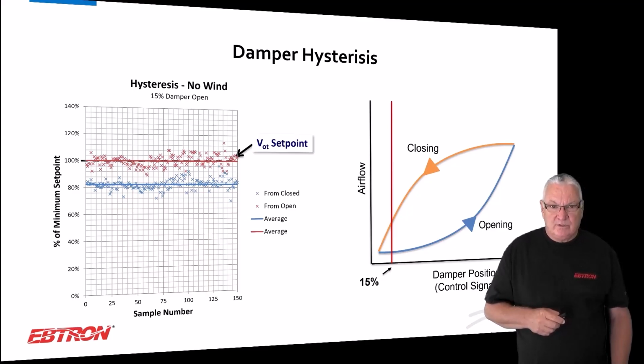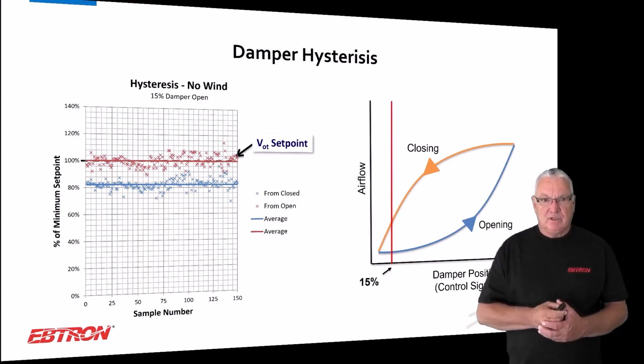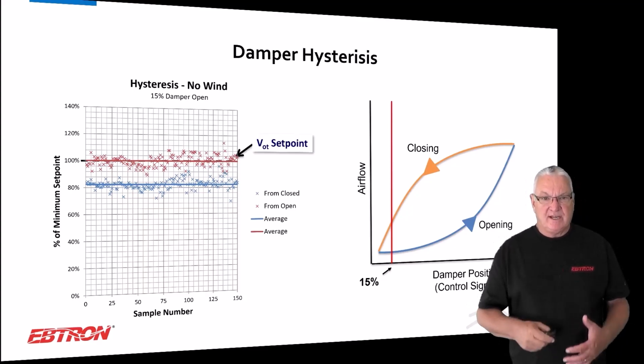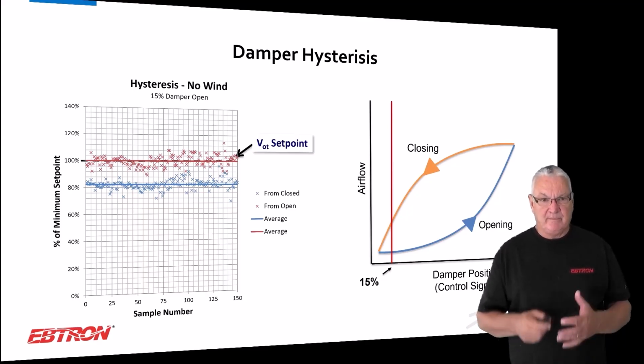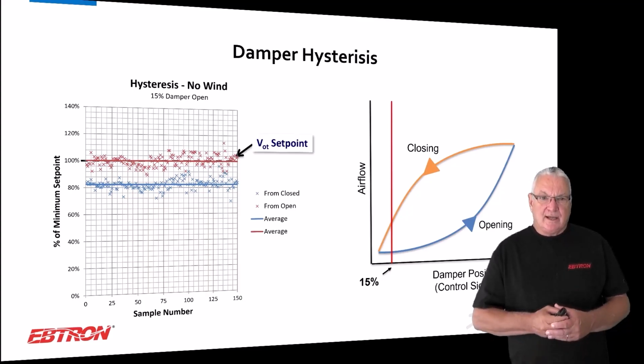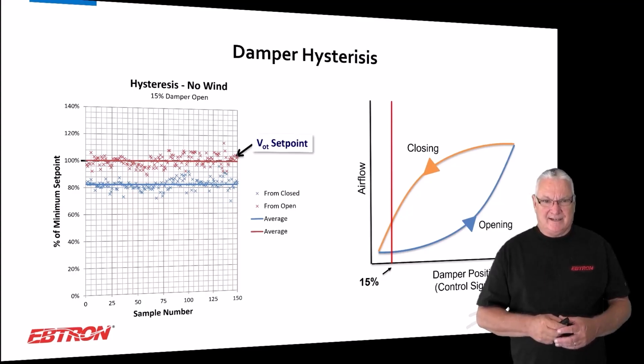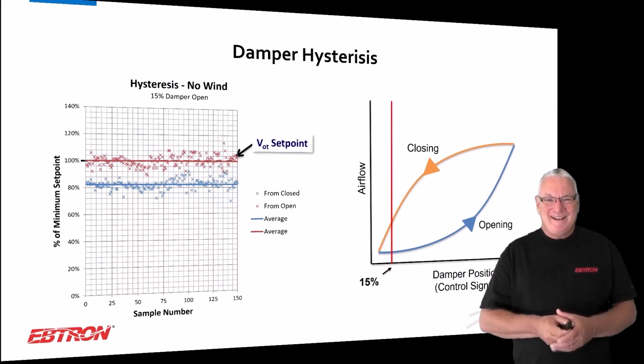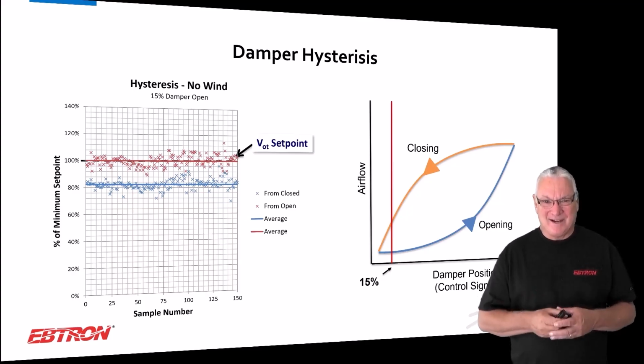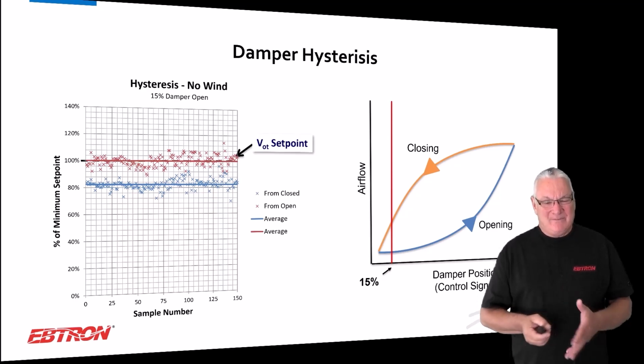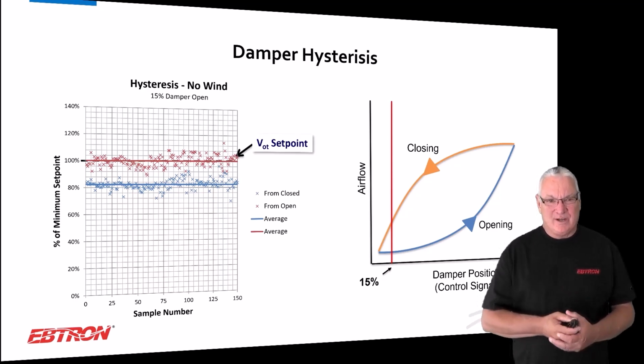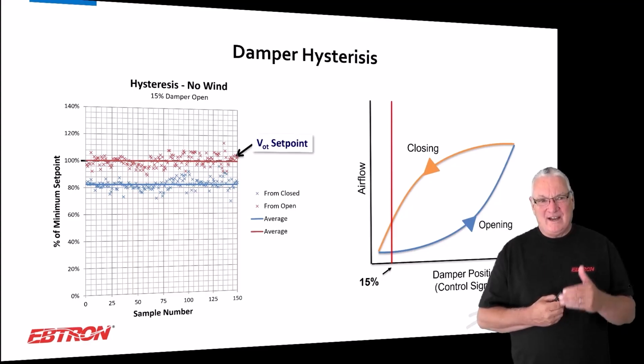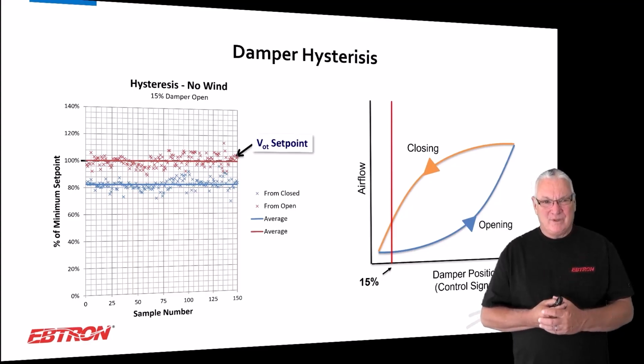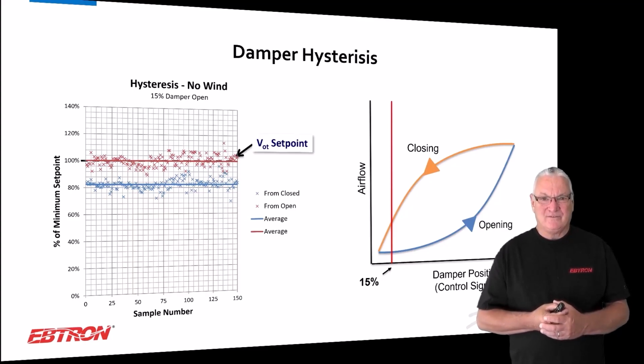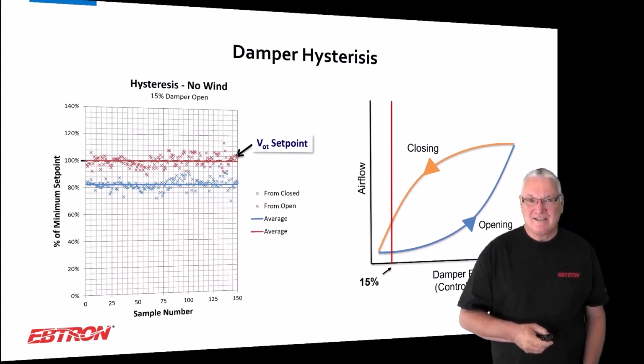If you look at the two data sets there, the red and the blue, the blue is where we took it from night setback, or closed, to 15% open and measured the outside air. And the red, we took it from 100% economizer back to that same 15% open, the same signal to the actuator. When we measure it, we have two very different populations that are 20% apart in flow. And that's just hysteresis. That's nothing else.